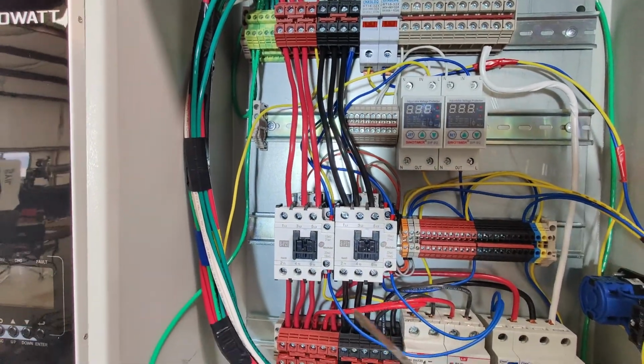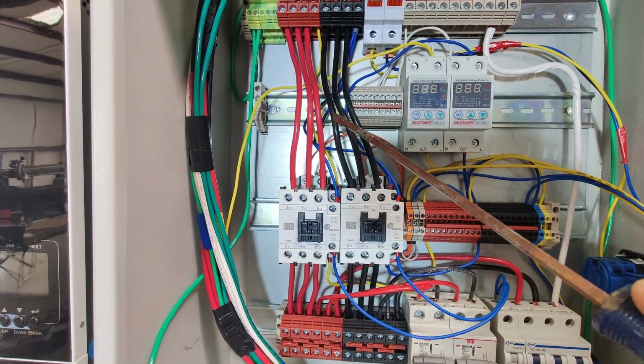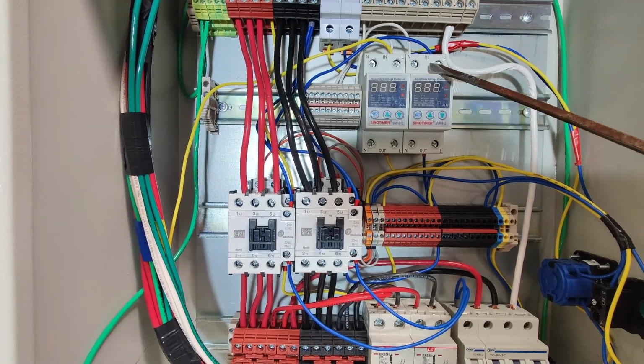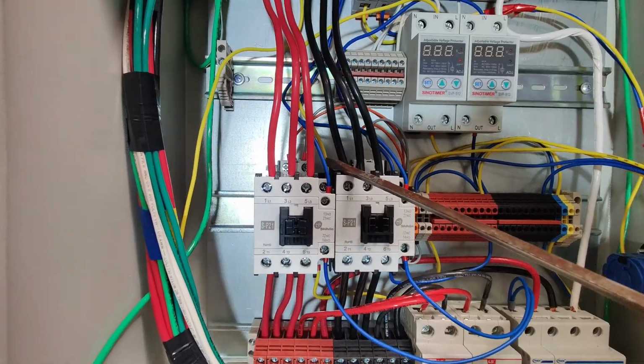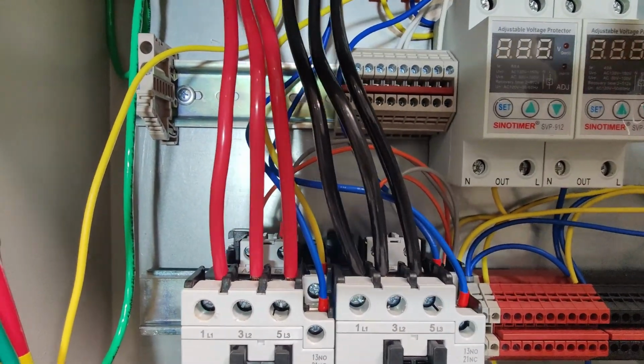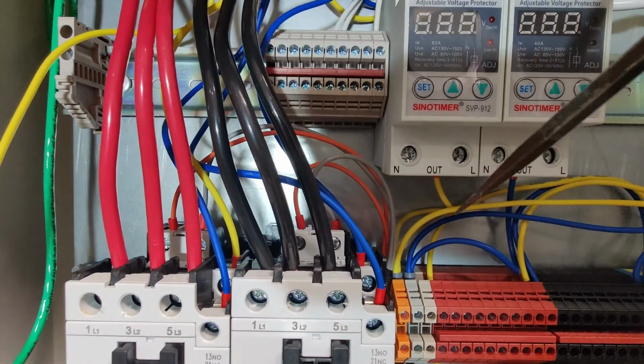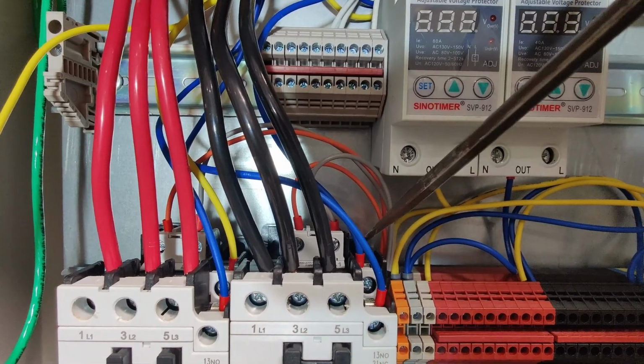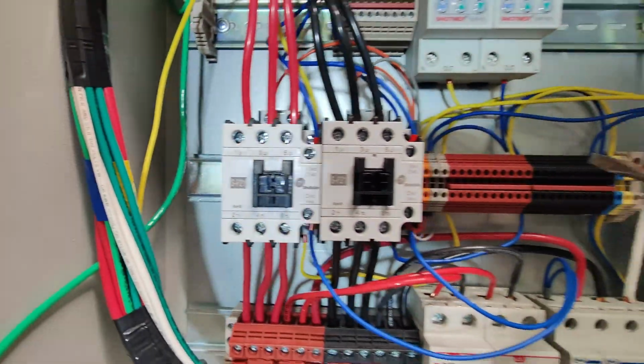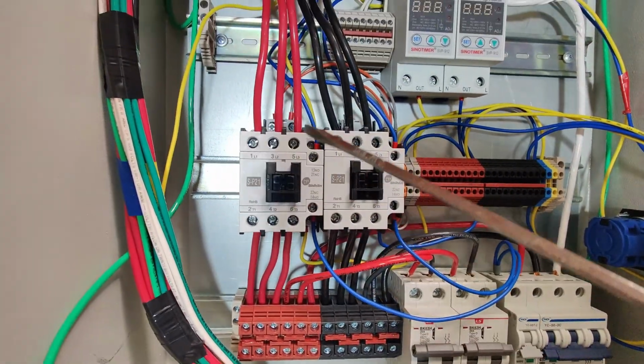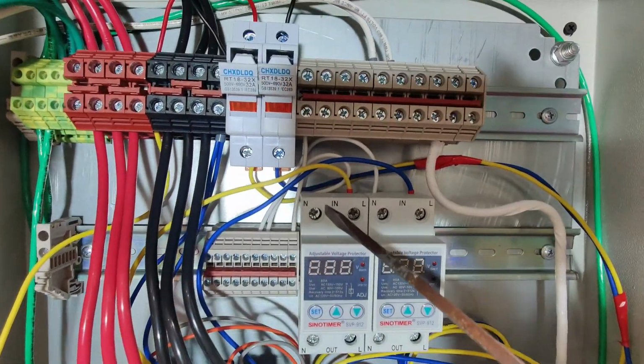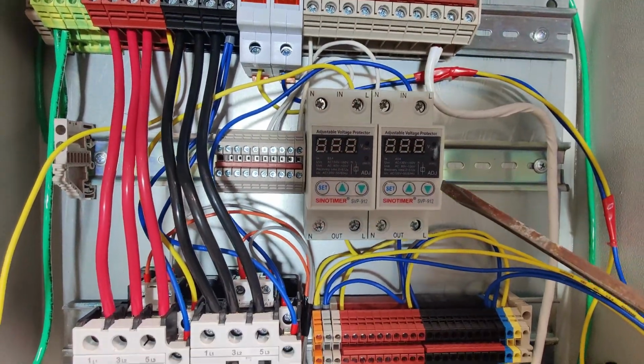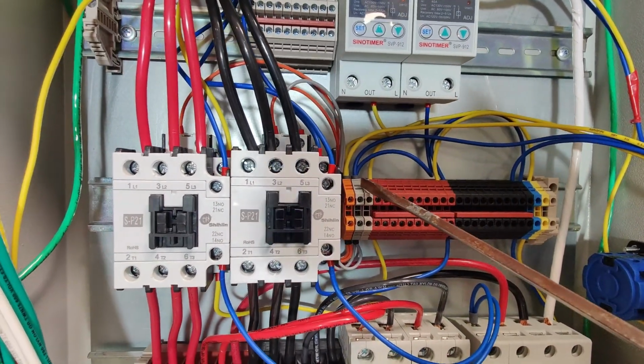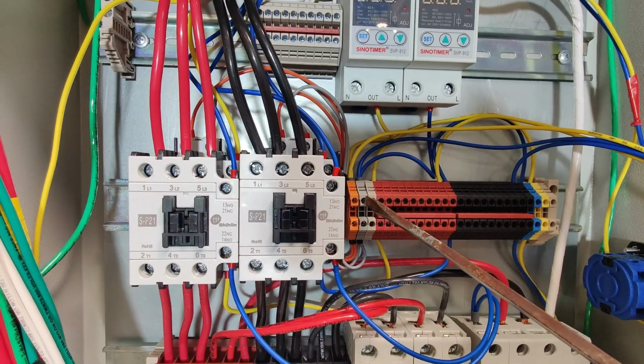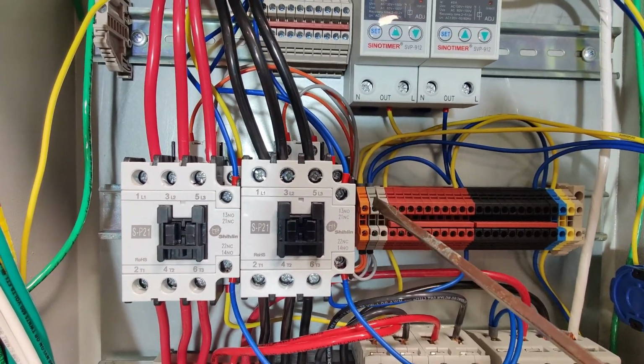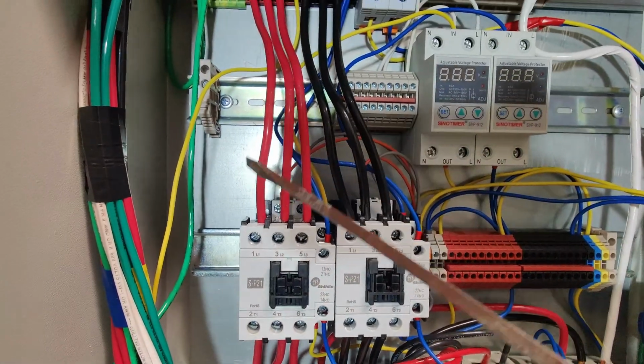So after I brought the wires out of the bottom side of the contactors, I brought them each up into the top side of these voltage protection relays. So you can see that yellow wire back there. So let's see if I can get in there. The yellow wire back here and the blue wire back here. And what that's doing is breaking the circuit that comes out from where it's switched over here, comes through here, comes up and around, goes into the top side of each voltage protection relay, and then comes out and goes over and goes into each one of these connectors here. This time I've used a yellow and gray connector, and that yellow and gray connector comes through here and then goes over and goes up into the top side of the contactor.